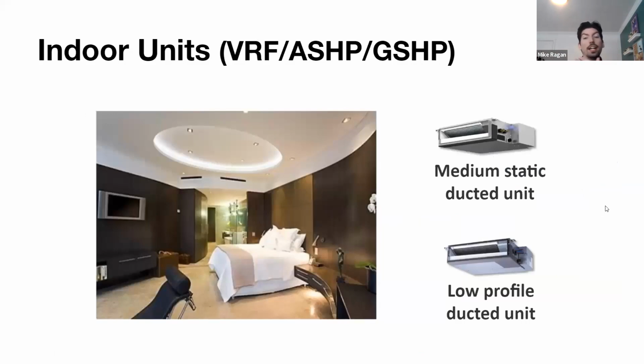And of course, now we're going to our ducted style units. A lot of people, when they think heat pumps and VRF, they think ductless. They're like, well, it's only refrigerant. We're not having air duct from the roof. This is a ductless system. The reality is the majority of fan coils that we're actually selling are going to be ducted units. And in fact, the most common style are the medium static ducted units, a very versatile unit that can go in conventional style ductwork applications. The only difference is it's being served by a refrigerant circuit as opposed to air ducts all the way to the roof.